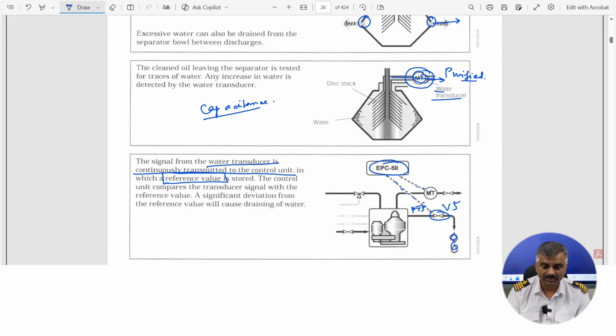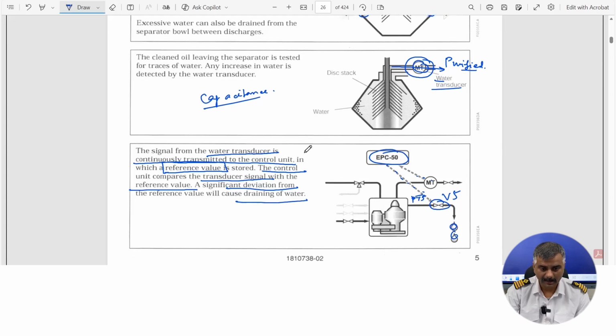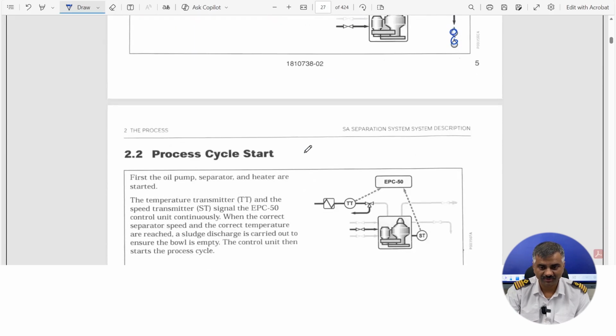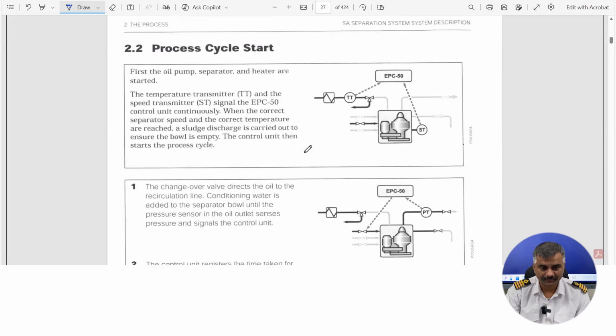That is why it is a very smart and advanced type of control system in EPC50, which takes the reference every time a water discharge takes place. The control unit compares the transducer signal with the reference value. When it sees a significant deviation from the reference value, at that time the draining of water will take place. So you see that valve V5 will open to discharge water.